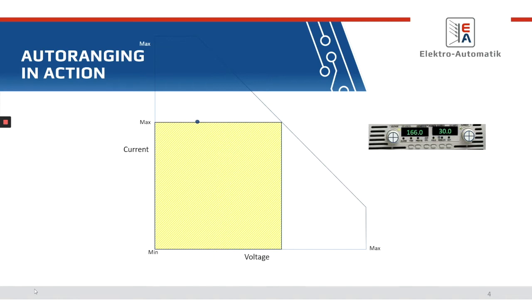That obviously gets worse when you get down into even lower voltages. Let's say at 166 volts, you're looking at 5 kilowatts. So here, you acquired a 15 kilowatt power supply and you're only actually able to get 5 kilowatts out of it. Okay. So this is just some of the limitations that come with a square operating curve power supply.